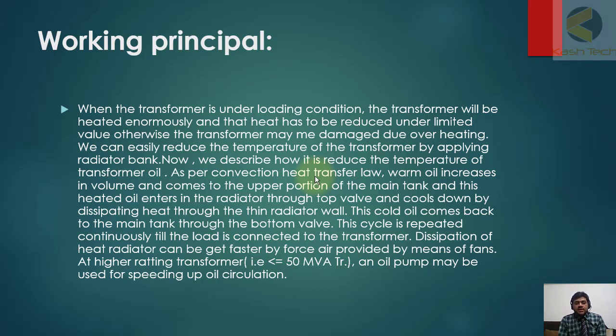This cycle is repeated and continues till the load is connected to the transformer. Dissipation of heat through the radiator can be made faster by forced air produced by means of fans at higher rating transformers. An oil pump may also be used for speeding up the oil circulation. This is basically how the radiators operate.